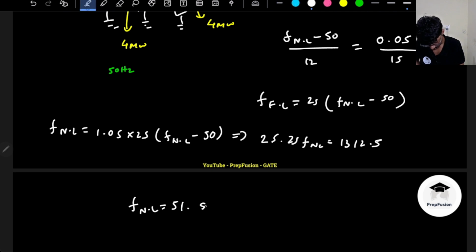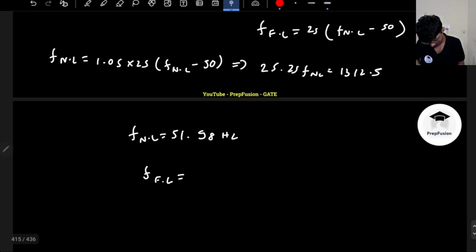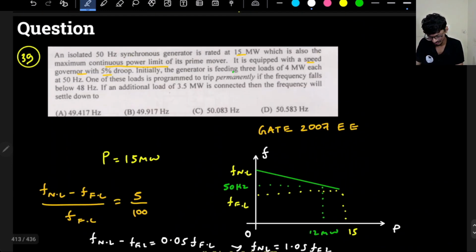These questions are actually pretty good. So what will my FFL be? FFL will be this value minus 50, times 25, which is 49.5 hertz. Now let's come back to the question.